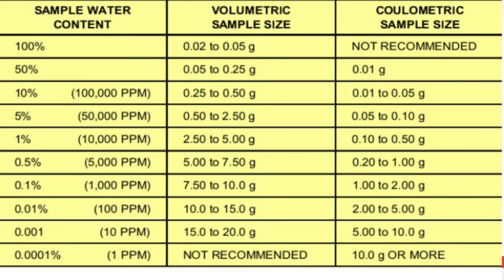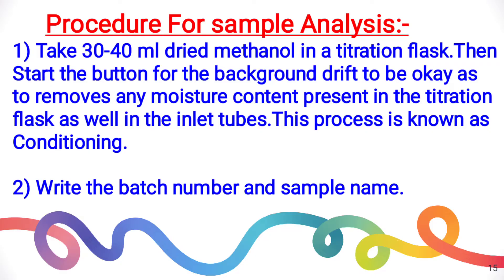How much sample can be used for the analysis of water content? A table is shown on the screen. For example, if your sample contains 100% water, then only 0.02 to 0.05 grams of the sample can be used for analysis. If 5% water is present in the sample, then 0.5 to 2.5 grams of the sample is used for analysis.